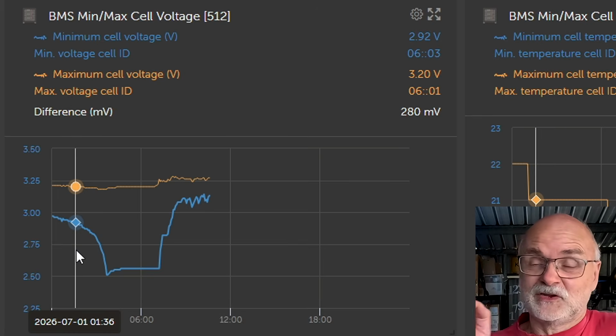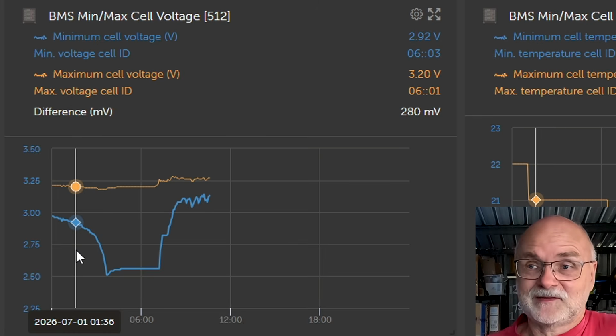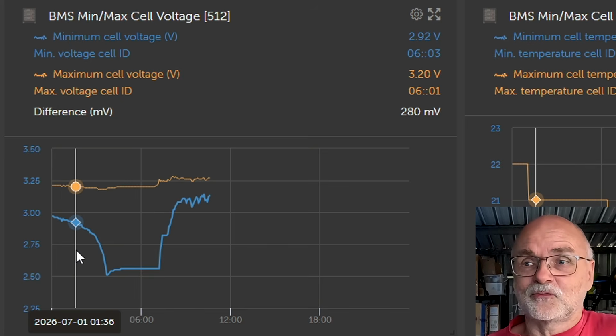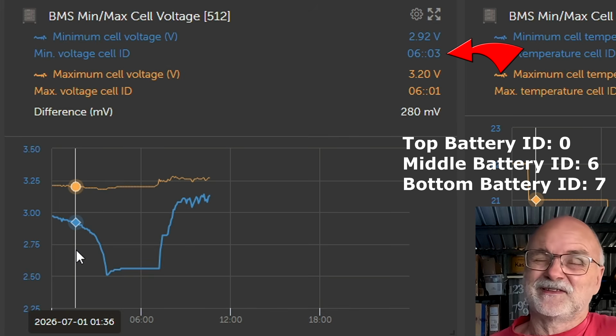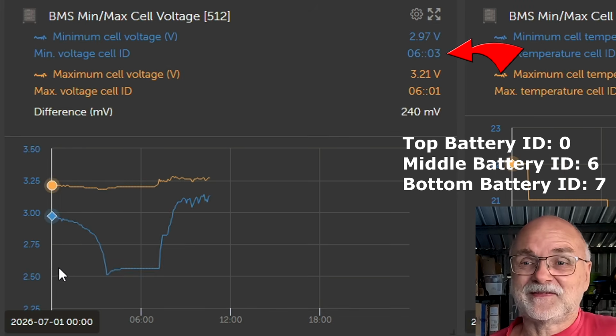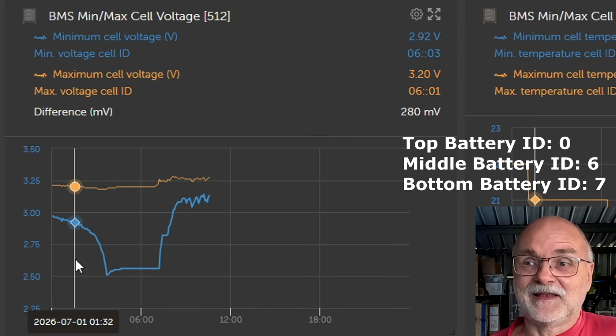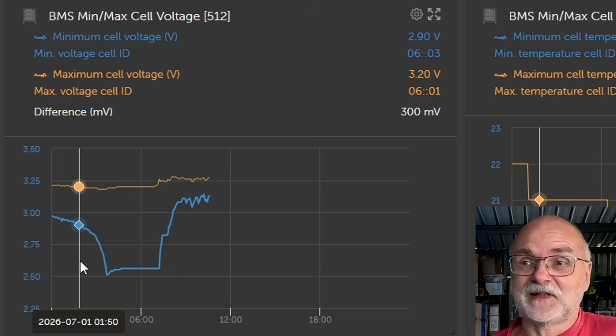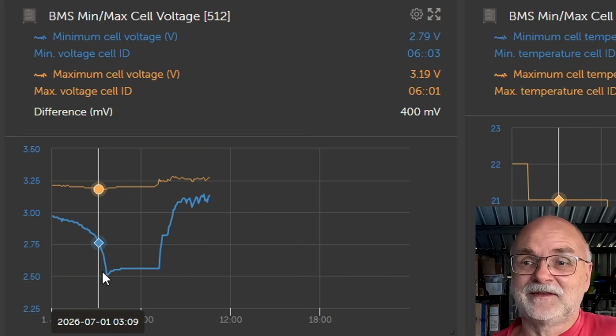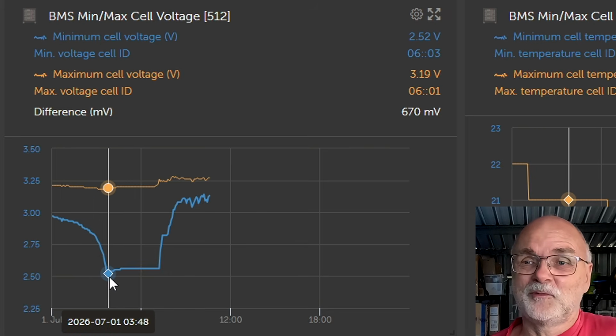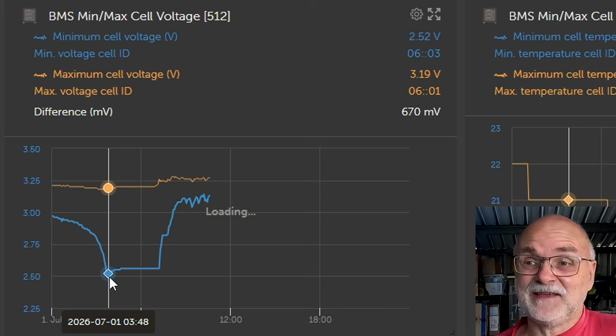This graph here shows us the BMS min and max cell voltages. Yeah, another advantage of the communication we have established for all three batteries in the battery shelf. You can see here that cell number 3 of battery number 6, which is the second battery. So battery number 6 is our middle shelf battery, and cell number 3 was the lowest, and you can see the cell voltage there, 2.9, 2.8, goes all the way down to 2.5. And the BMS has actually disconnected this battery during the night.